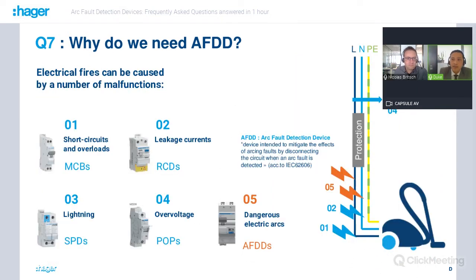Electrical fires have a good proportion of fires in general. The causes of electrical fires that we already know are short circuits and overloads, leaking currents, lightning, and overvoltage, which are protected by MCBs, RCDs, SPDs, and POPs. However, we can see in number 5 the arc faults, the dangerous electrical arcs, which were described and explained in the last questions, now protected and needing to be protected by AFDDs.